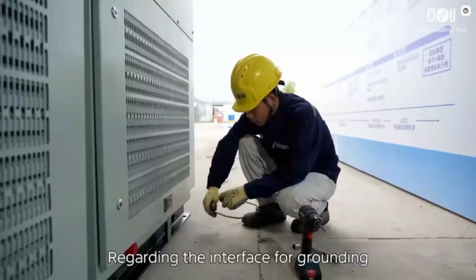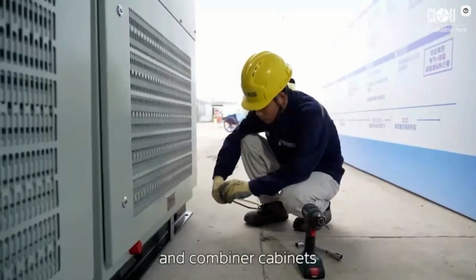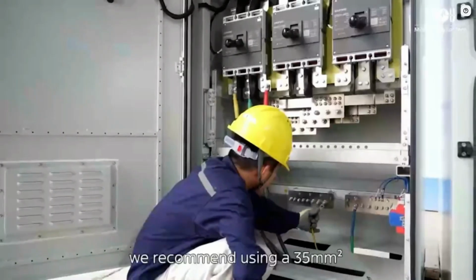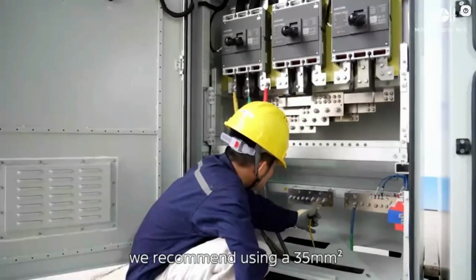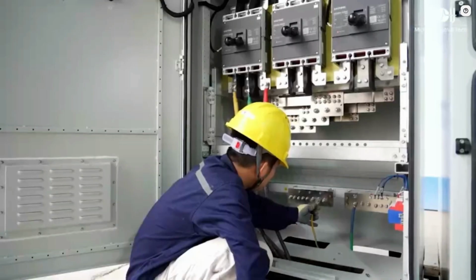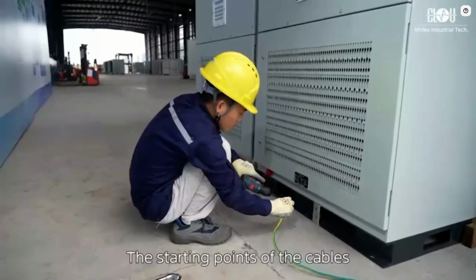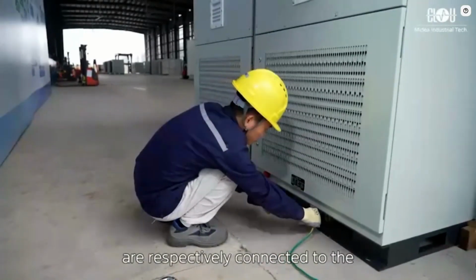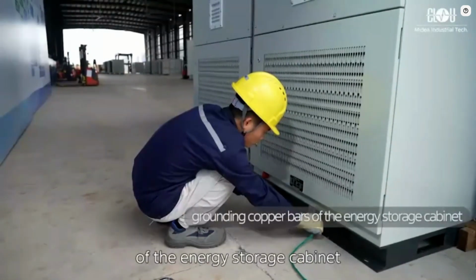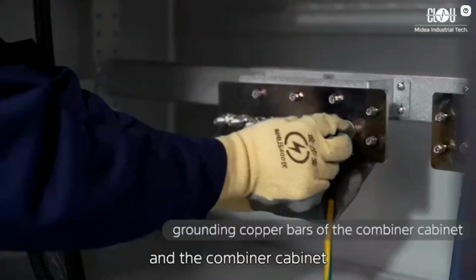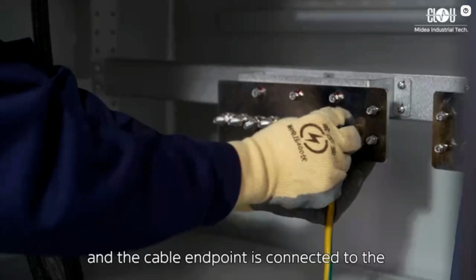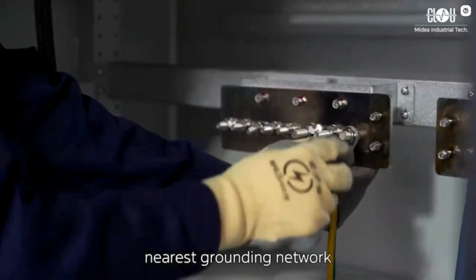Regarding the interface for grounding energy storage cabinets and combiner cabinets, we recommend using a 35 square millimeters yellow-green cable. The starting points of the cables are respectively connected to the grounding copper bars of the energy storage cabinet and the combiner cabinet, and the cable endpoint is connected to the nearest grounding network.